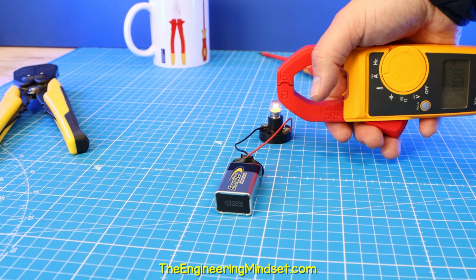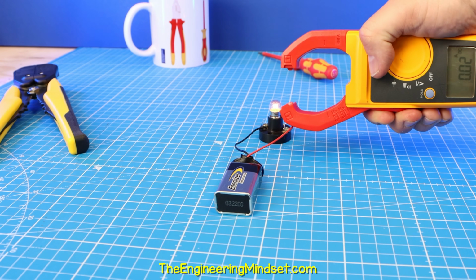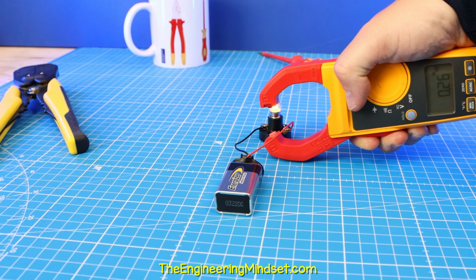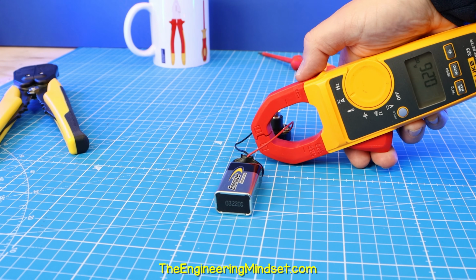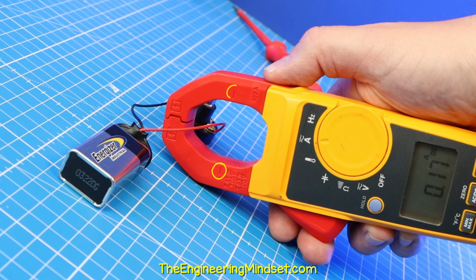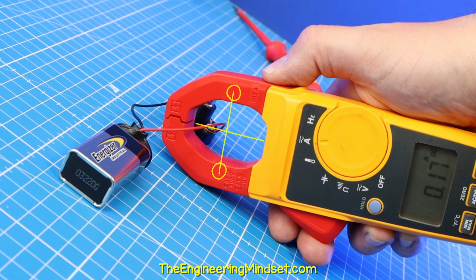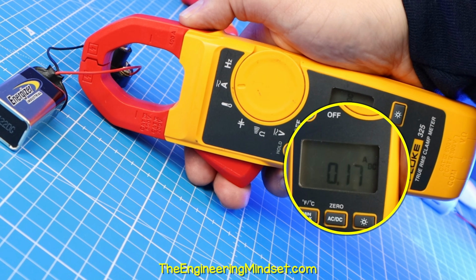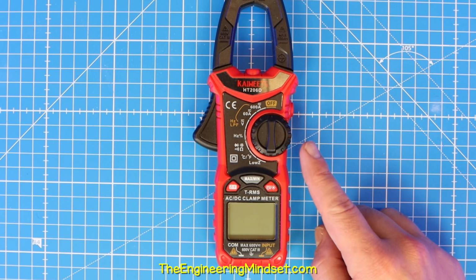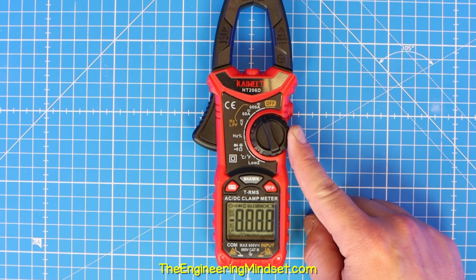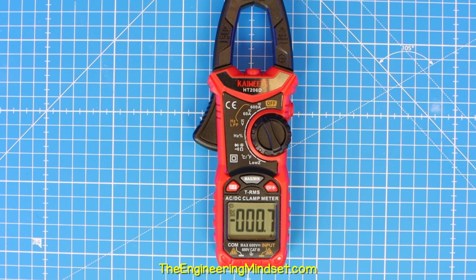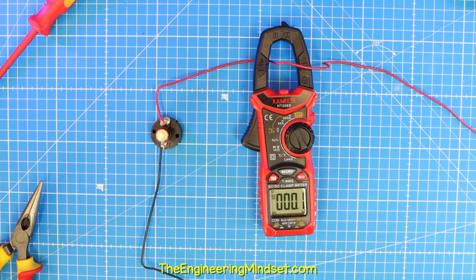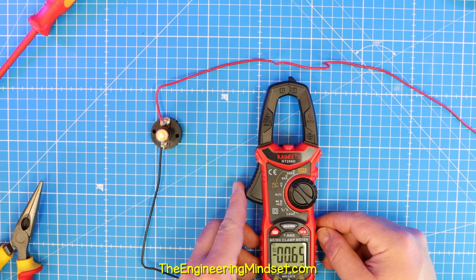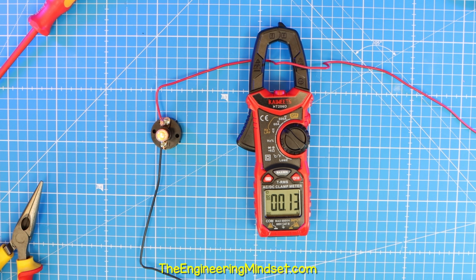Then, keeping our hand behind the guard, open the clamp and place it around the wire. Then release the trigger and check the jaws are closed. Try to keep the wire between the center lines for the most accurate reading. The meter then displays the current value. If you have a manual range meter, you'll need to choose the most appropriate range, or start with the highest, and if the current is lower than the next range, switch down to this for a more precise reading.